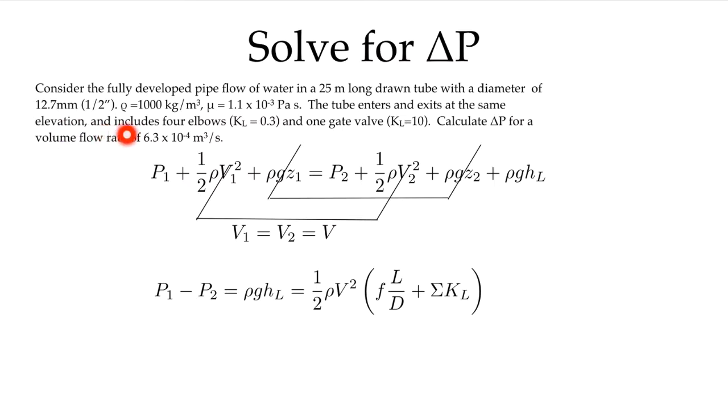The tube enters and exits at the same elevation and includes four elbows. I'm giving the loss factor for each elbow as 0.3, and it has one gate valve with a loss factor of 10. The question is to calculate ΔP for a volume flow rate of 6.3×10⁻⁴ m³/s.